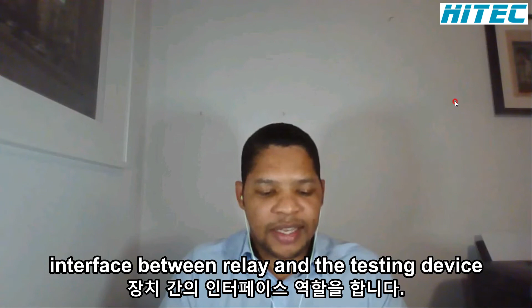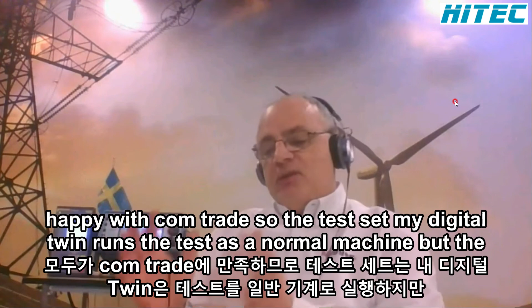We have two digital twins, to make it simple: one is a relay test set, and one is a digital twin for the protection relay. These two have to be connected together. At the moment the interface between the test set has been decided, driven by Siemens, using IEC 61850 with Comtrade—everybody's happy with Comtrade. So the test set, my digital twin, runs a test as a normal machine, but the generators aren't really there; the generators are in a Comtrade file, and this file is passed manually into the Siemens environment. So at the moment the interface works like this, but we're just at the beginning of this interaction. Later on, we hope to have a direct interaction between the two digital twins, so you can virtually connect them together and run the test as you're used to in reality.